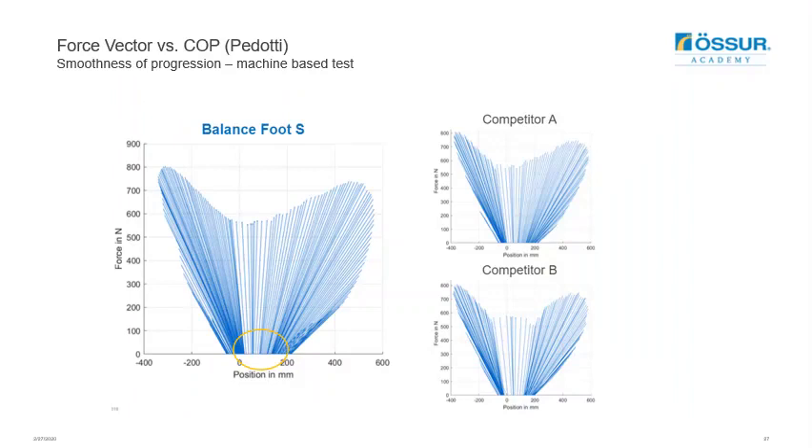The smoothness of progression of the Balance Foot S was compared to two competitive feet using machine-based testing and Pedotti diagrams. In early stance, there is a very smooth ramp up of load at initial contact with the Balance Foot S, whilst allowing the weight lines to progress forward on the heel — potentially reducing the need for users to stabilize their knee and allowing load to enter the socket more naturally. The competing feet show a distinct amount of time on the heel before quickly transitioning to the mid foot and then loading again on the toe. The Balanced Foot S has the most evenly distributed force vectors and the smoothest increase in toe loading, and users are anticipated to notice this smoothness as they walk.